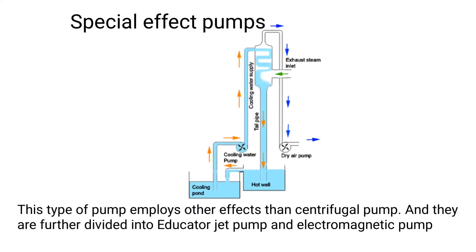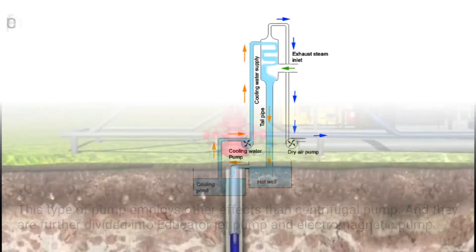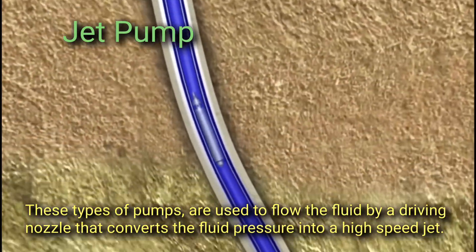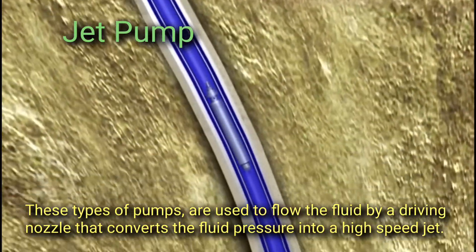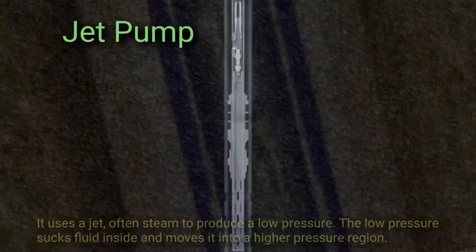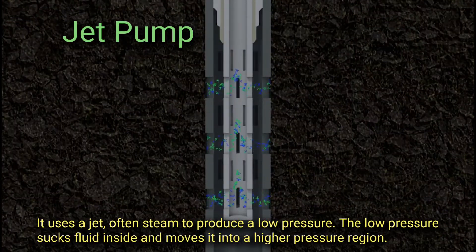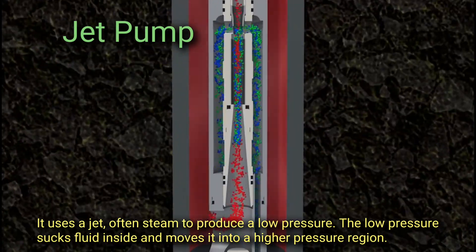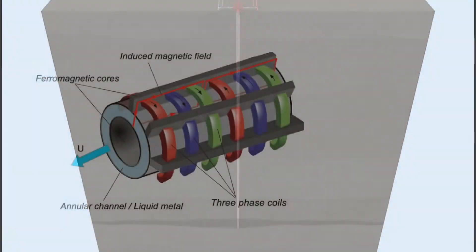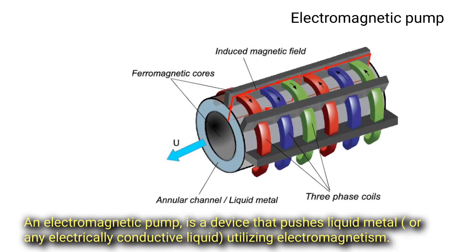Special effects pumps employ other effects than centrifugal action and are further divided into eductor jet pumps and electromagnetic pumps. Jet pumps are used to flow fluid by a driving nozzle that converts the fluid pressure into a high-speed jet. It uses a jet — often steam — to produce a low pressure. The low pressure sucks fluid inside and moves it into a higher pressure region.